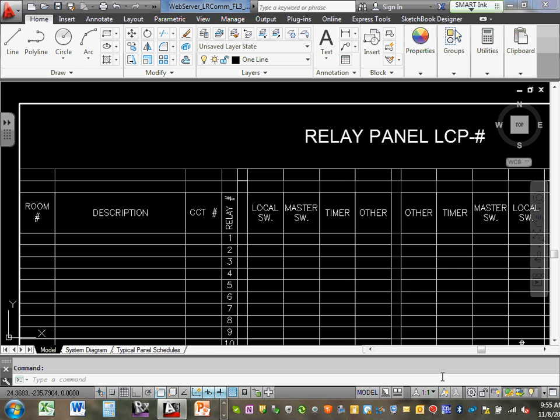We ask for the circuit that you're feeding from, right? Or the circuit that it's coming from. And we'll back up a little bit. When dealing with low voltage control, anytime I feed from a second panel, I have to barrier it. I can't bring a feed from 2 different panels into a low voltage panel and not have a physical metal barrier in between. It has to be. And if I'm going to bring life safety in from a life safety panel, I have to barrier that as well. So every time I feed from a different panel, I have to put a physical break in the panel.